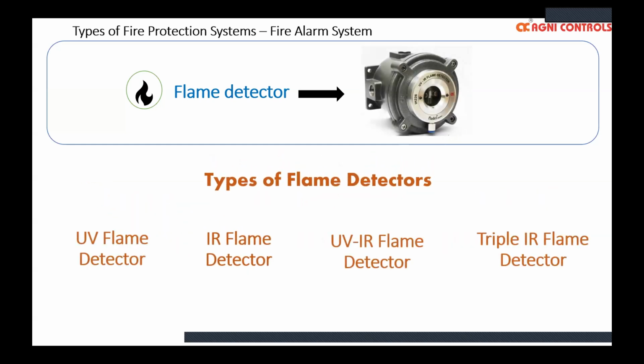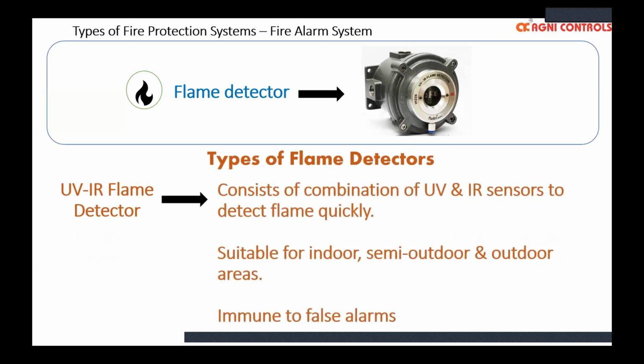So for that purpose, a combination of UV and IR sensors is used in the UV IR flame detector. As the name suggests, it has a combination of UV and multiple IR sensors to confirm whether it's an actual fire or a false source. These detectors are suitable for both indoor and outdoor applications. And since multiple sensors confirm a fire, these detectors are more immune to false alarm sources.